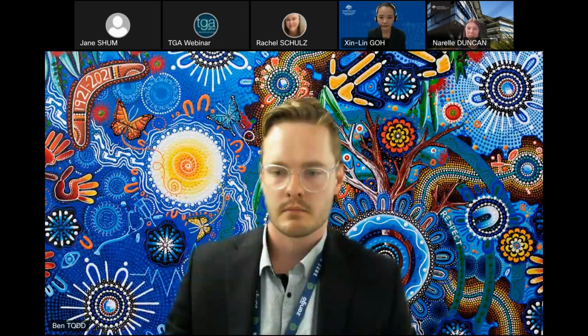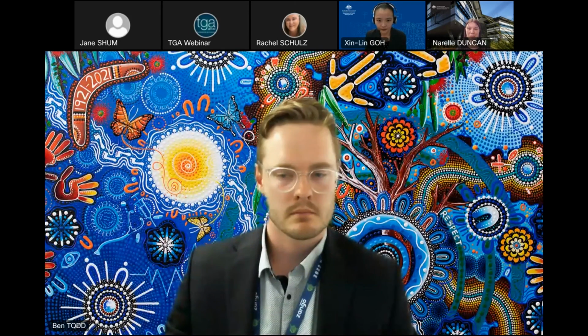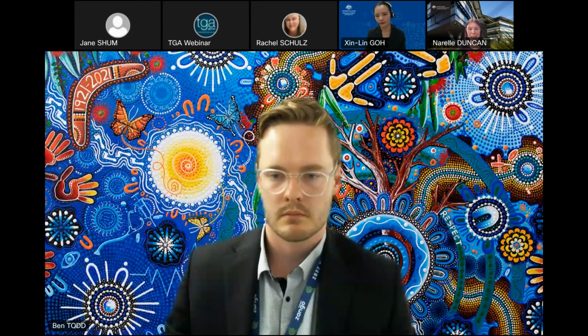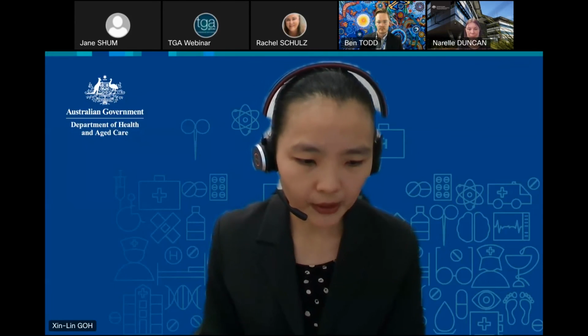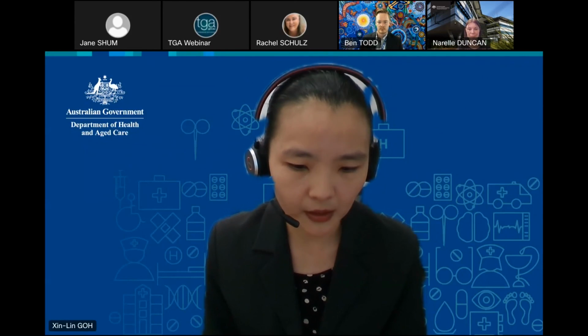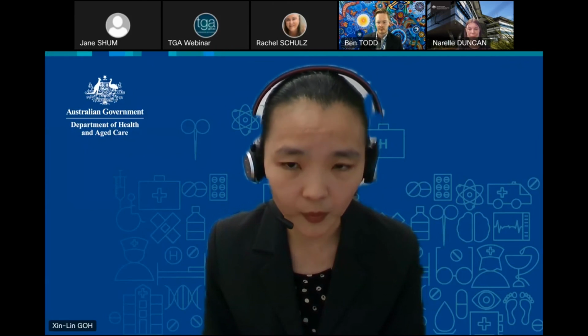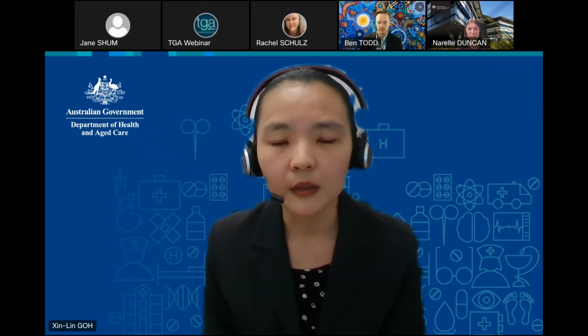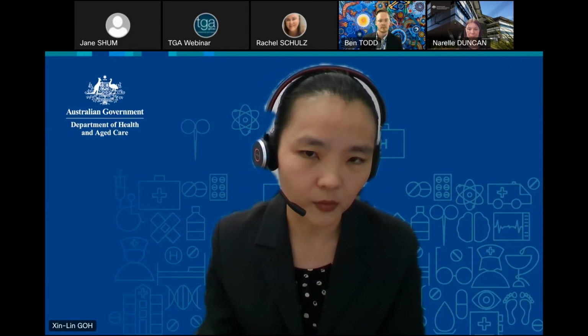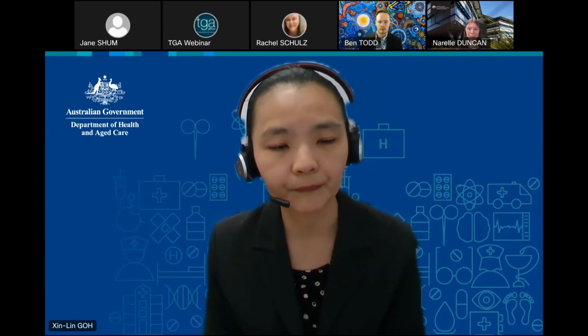Okay, our next question is, if the overseas manufacturer reclassified their product due to the update of the safety, would this mean automatic reclassification under TGA? No, so the classification of a product would be based on classification rules within our medical device regulatory framework. Having said that, we are largely aligned with Europe. So it really depends on what the change is, and I think the sponsor will need to refer to our classification rules and make a determination if that classification has changed.